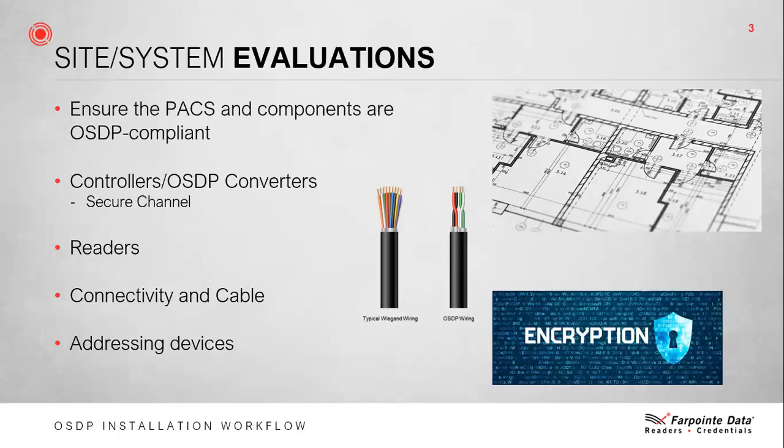When choosing your physical access control system, make sure to check their OSDP deployment capabilities. While OSDP is a communication protocol between hardware — readers and controllers specifically — you also need to make sure that your system software can support OSDP. For controllers, you'll need to determine that the controllers you plan to deploy support OSDP. Not all system manufacturers manufacture their own controllers, and not all controller manufacturers support OSDP natively or may only support OSDP in specific topologies. For example, some controller manufacturers support OSDP using RS-485 but only in a point-to-point topology and do not support the multi-drop option.